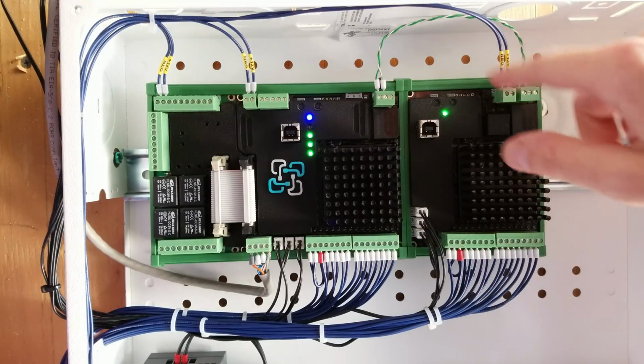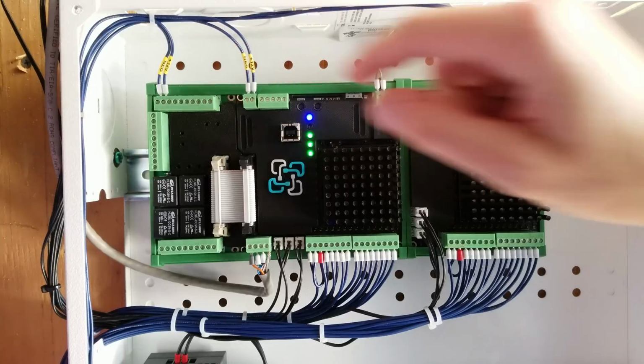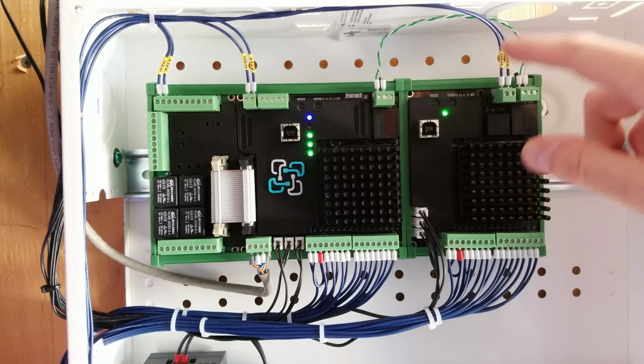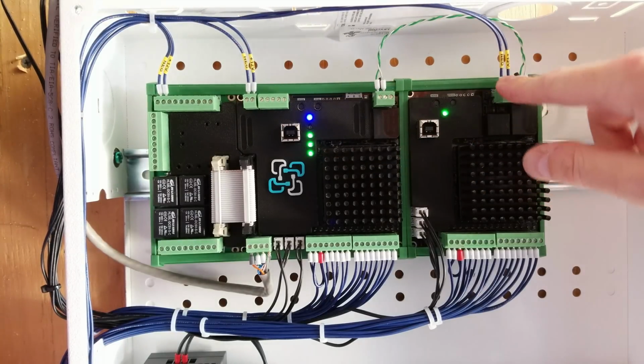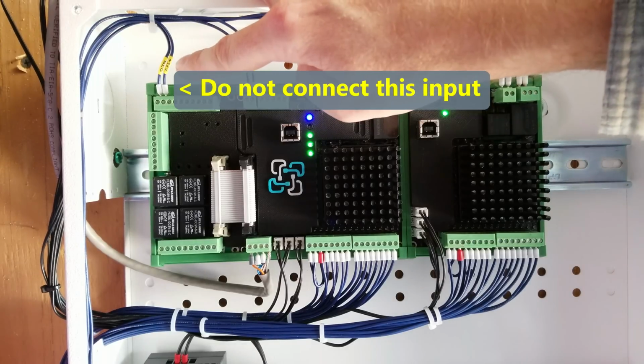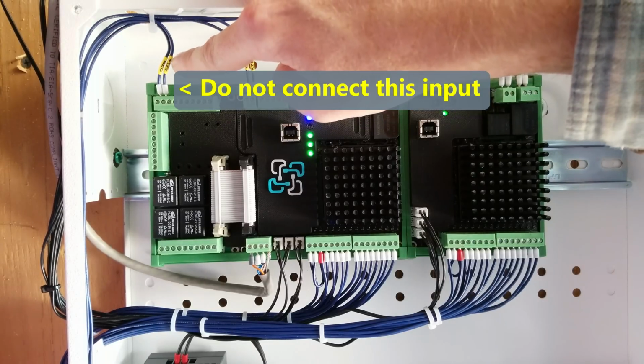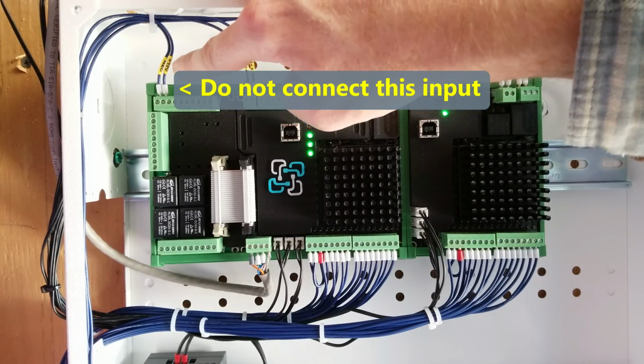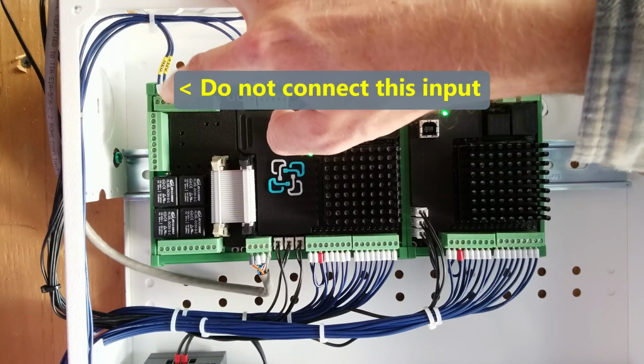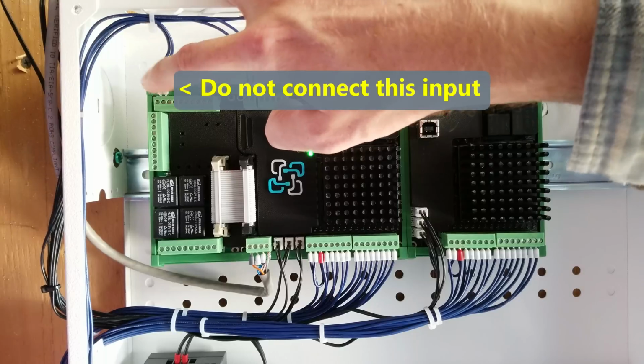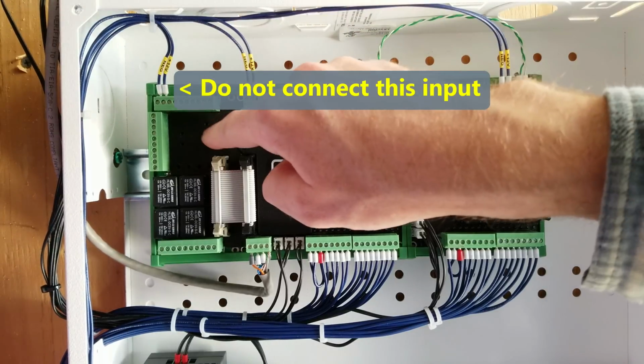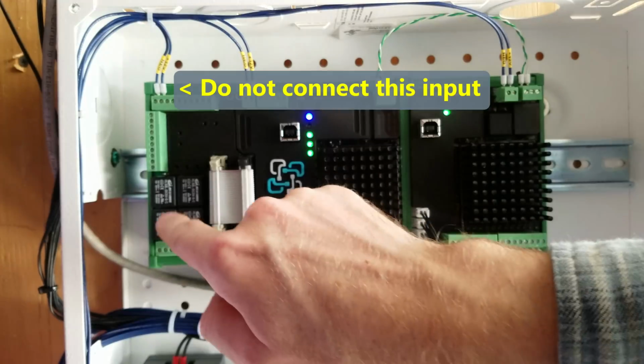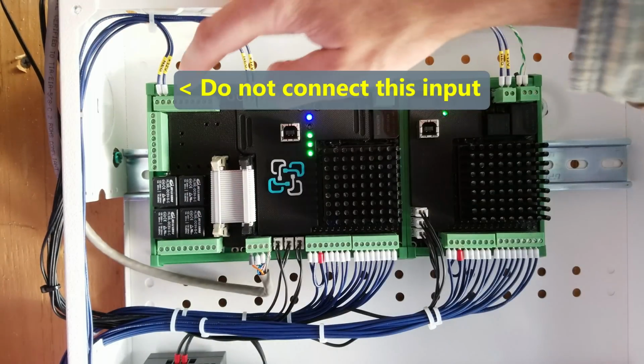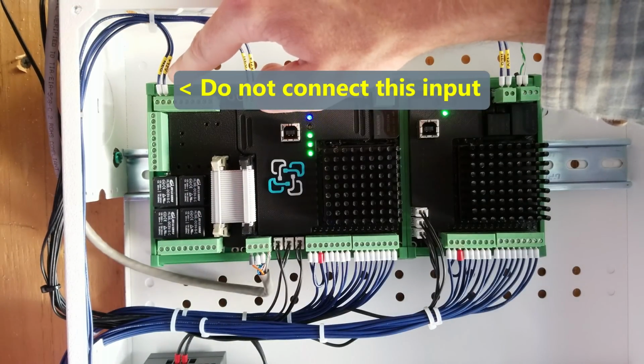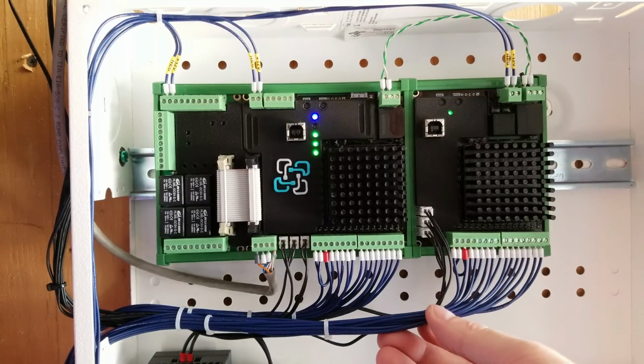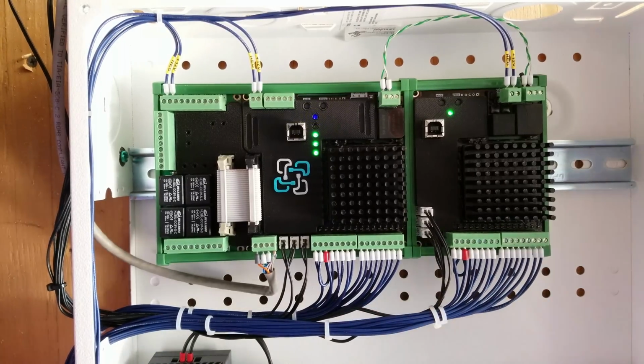I also went and labeled all of the 12-volt inputs. That way there is no confusion. Again, thank you to the person who recommended the heat shrink. One thing to add too is that it was pointed out by Batrium to me that you do not need the 12-volt supply connected on the expansion board unless you are utilizing the MOSFET outputs. If the only thing you're using are the relays, it's actually best not to connect the supply inputs. That being said, this is a very, very nice and clean cabinet that is set up here.